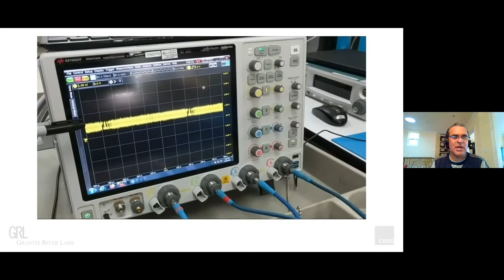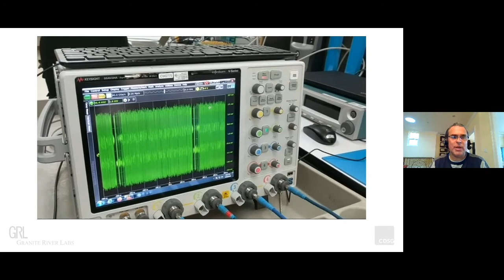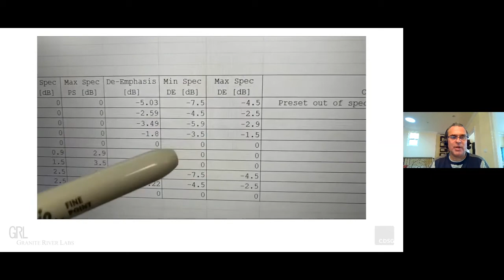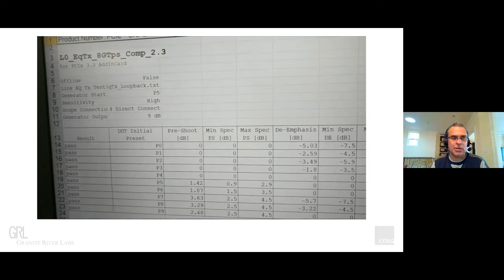It's pretty much the same process. I'm confirming on the scope that it's doing P0 testing for the transmitter. The BERT requested to go into P0, the device responded back during link training, and the scope captured and analyzed that. It goes through all presets from P0 to P9, corresponding with all the measurements for pre-shoot and emphasis defined in the spec to indicate pass or fail - and everything passes for this device under test.